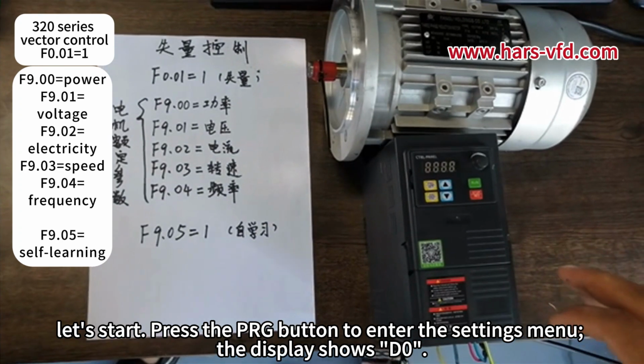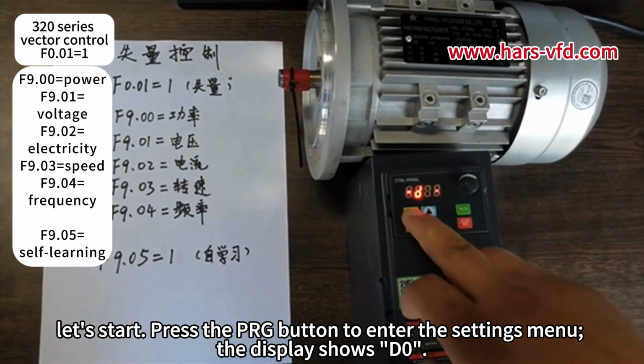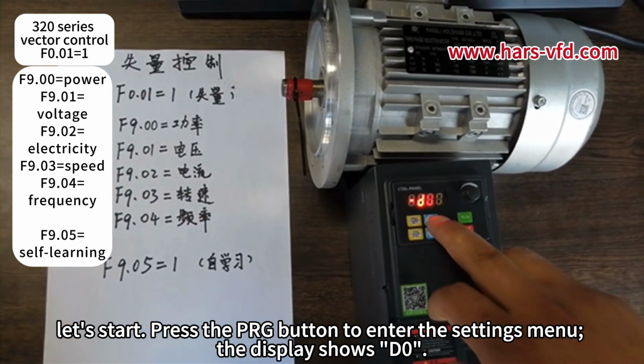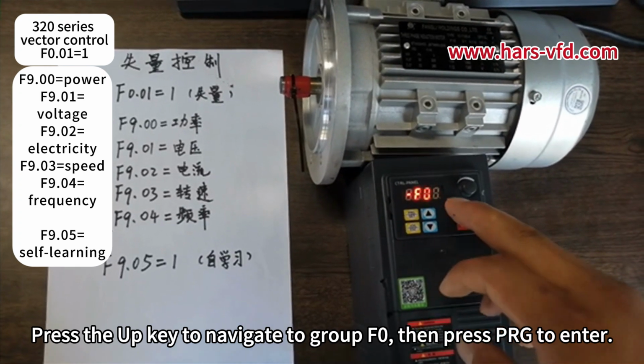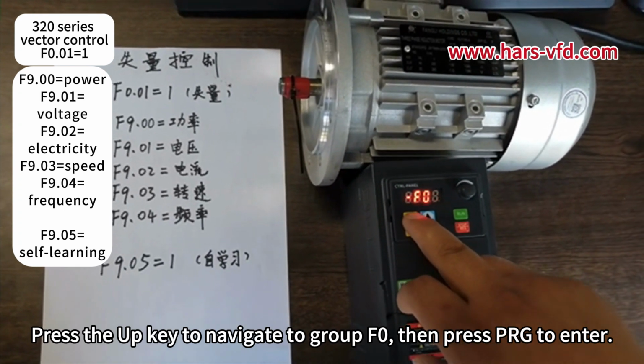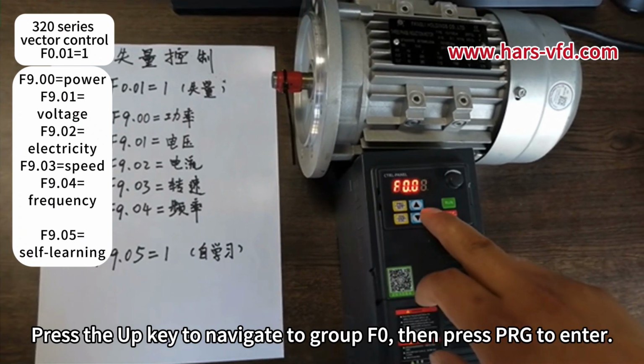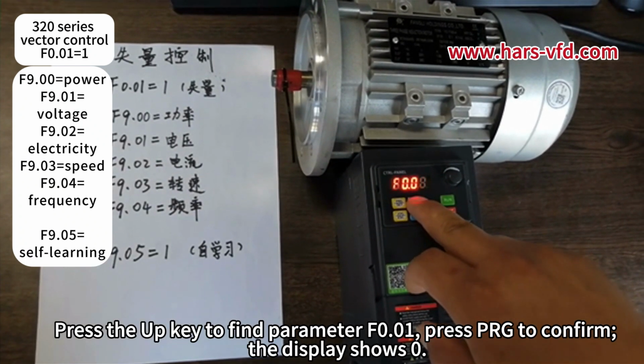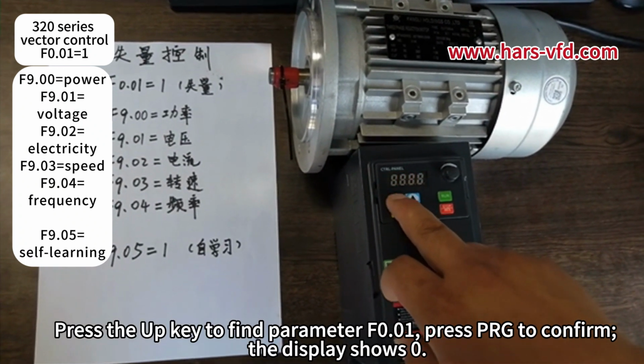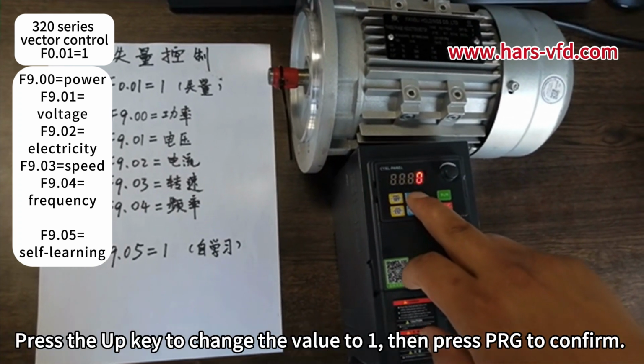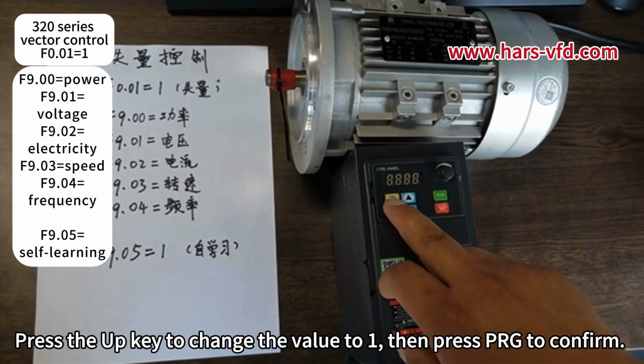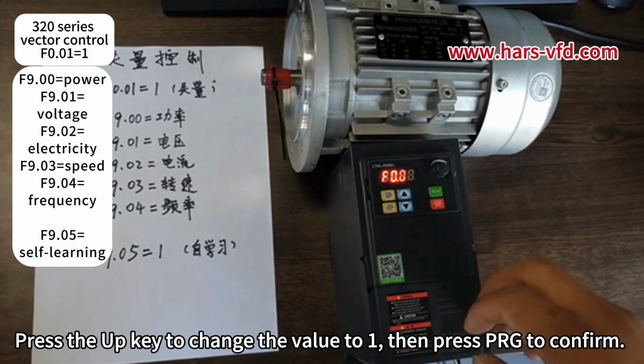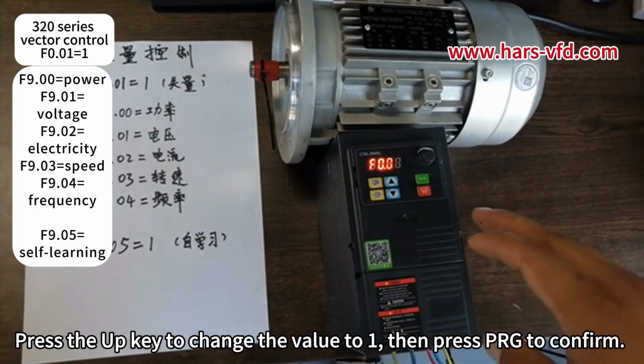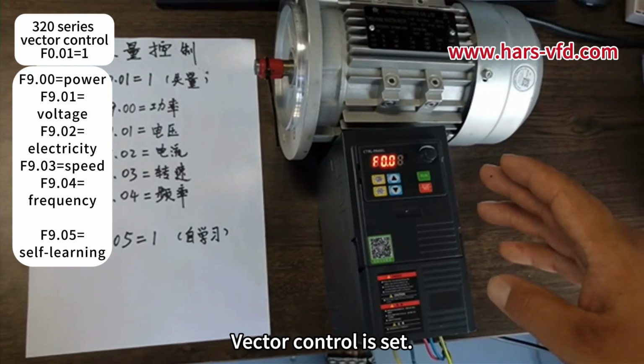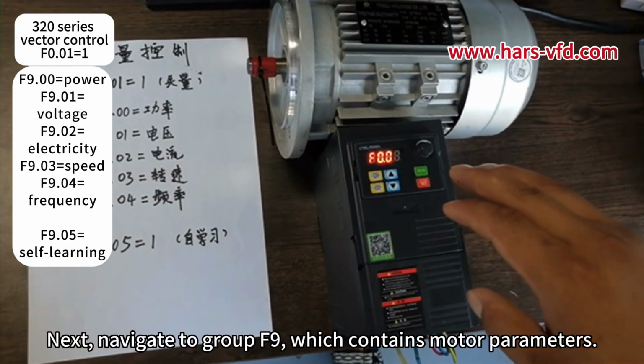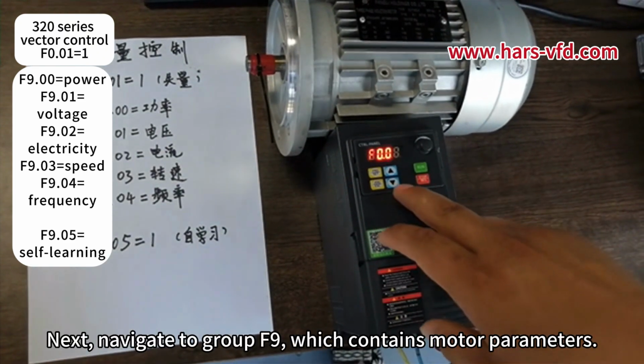Let's start. Press the PRG button to enter the settings menu. The display shows D0. Press the up key to navigate to group F0, then press PRG to enter. Press the up key to find parameter F0.01, press PRG to confirm. The display shows 0. Press the up key to change the value to 1, then press PRG to confirm. Vector control is set. Next, navigate to group F9, which contains motor parameters.